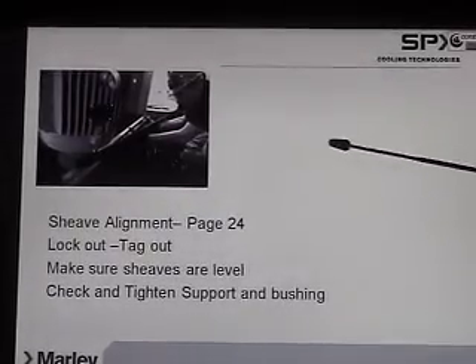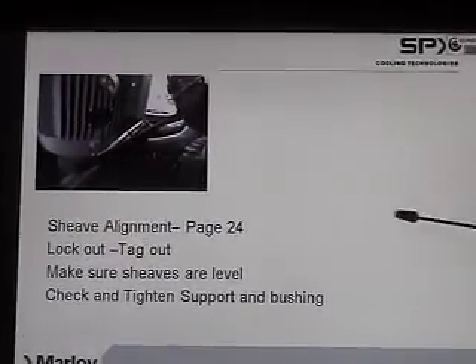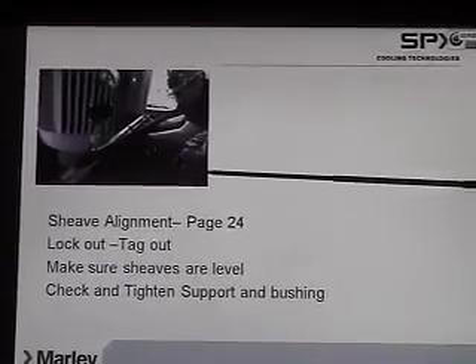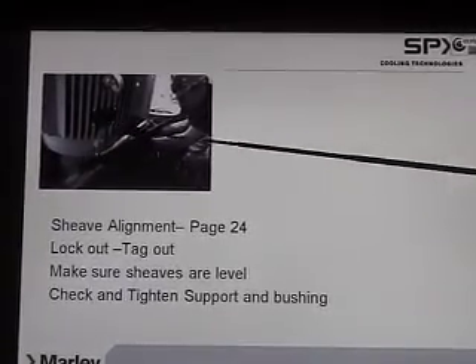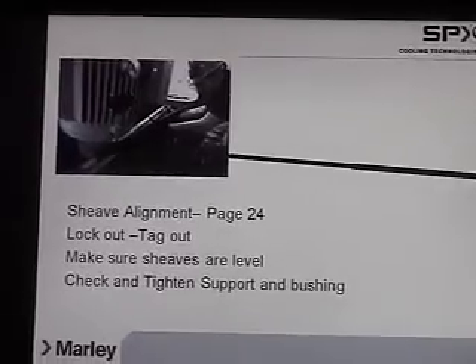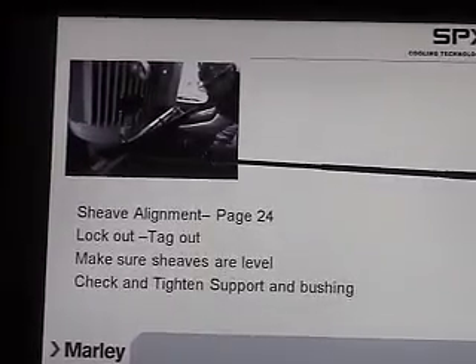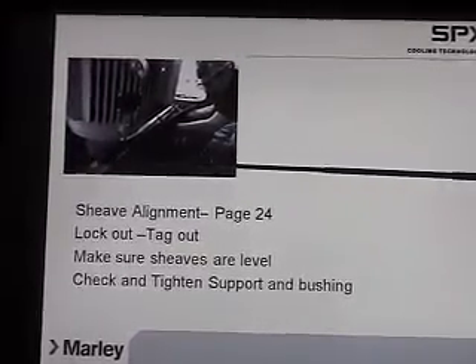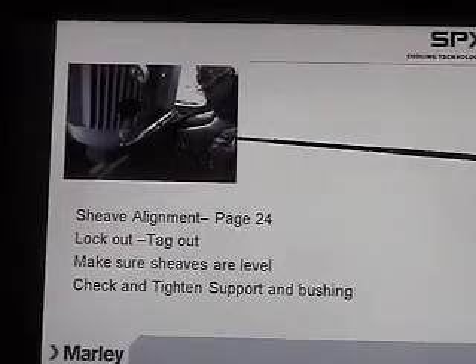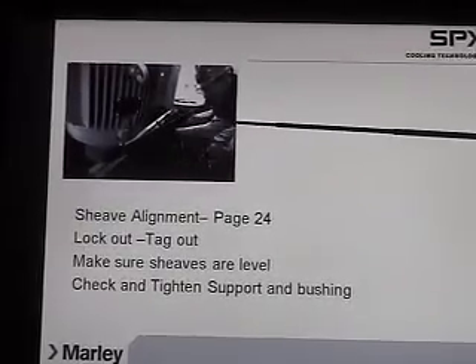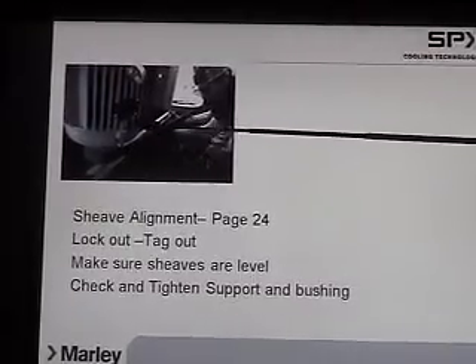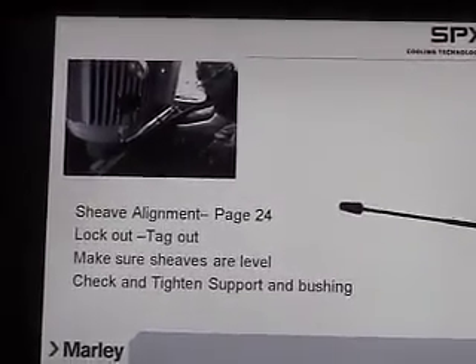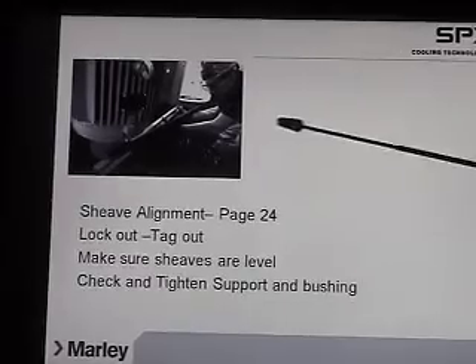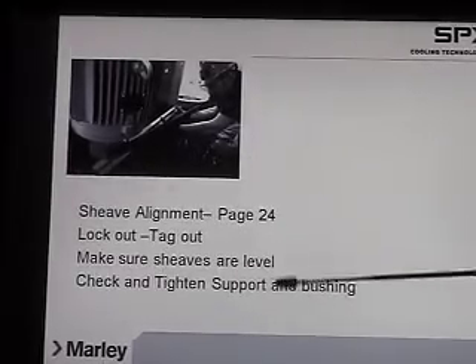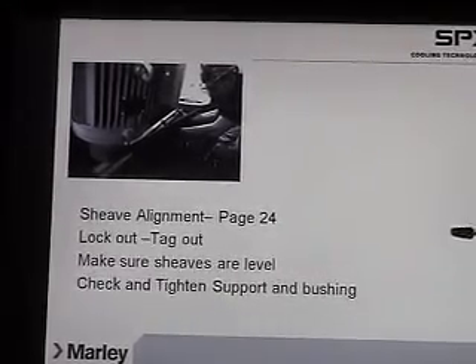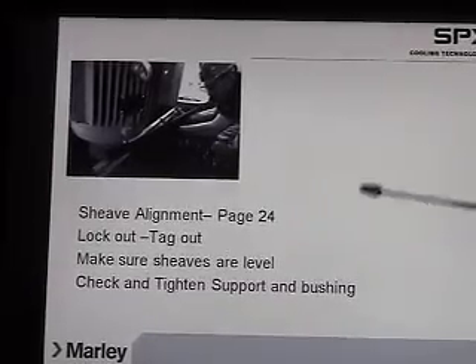Page 24 has the sheave alignment. You'd put a straight edge between the motor sheave and the fan sheave back here, and you'd want to be all in the same plane with all four corners, or four points on your straight edge, touching the fan and motor sheave. And then you would want to check and tighten your bushings and the supports, the bushings in the sheaves.